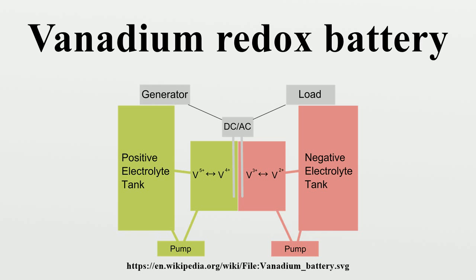Sulfuric acid-based vanadium batteries only work between about 10 to 40 degrees Celsius. Below that temperature range, the ion-infused sulfuric acid crystallizes. Round-trip efficiency in practical applications is around 65 to 75%.